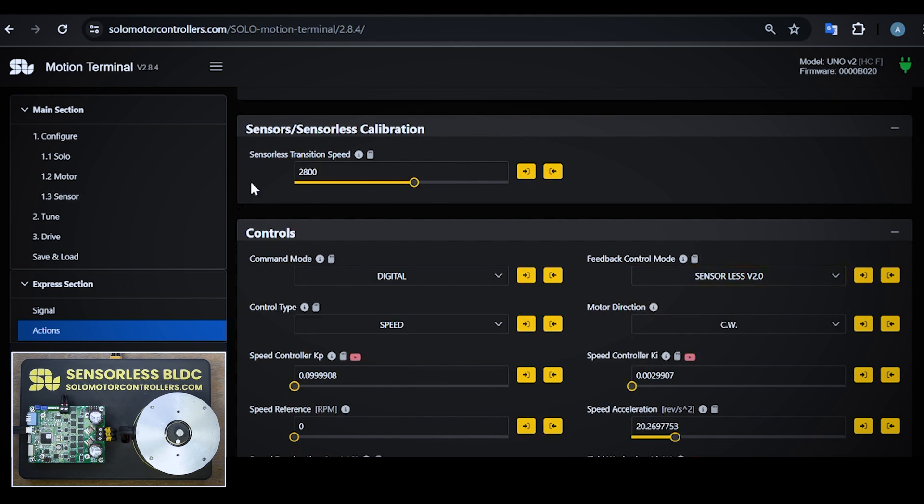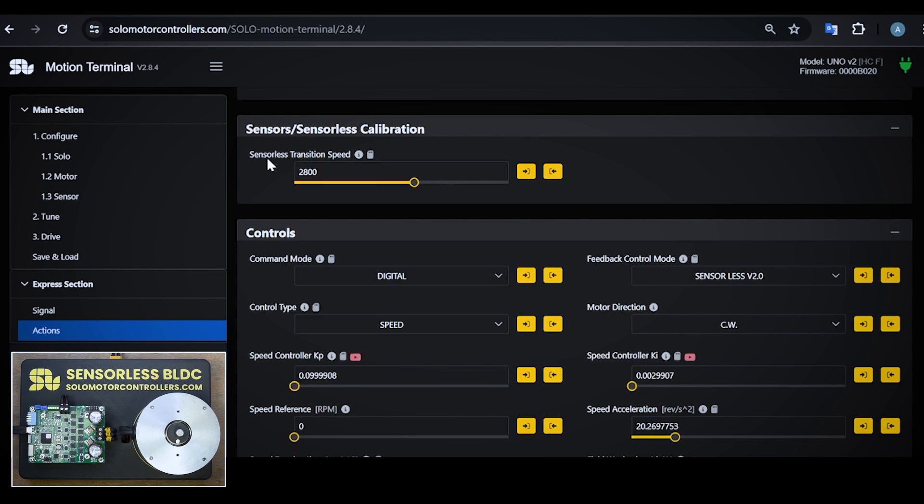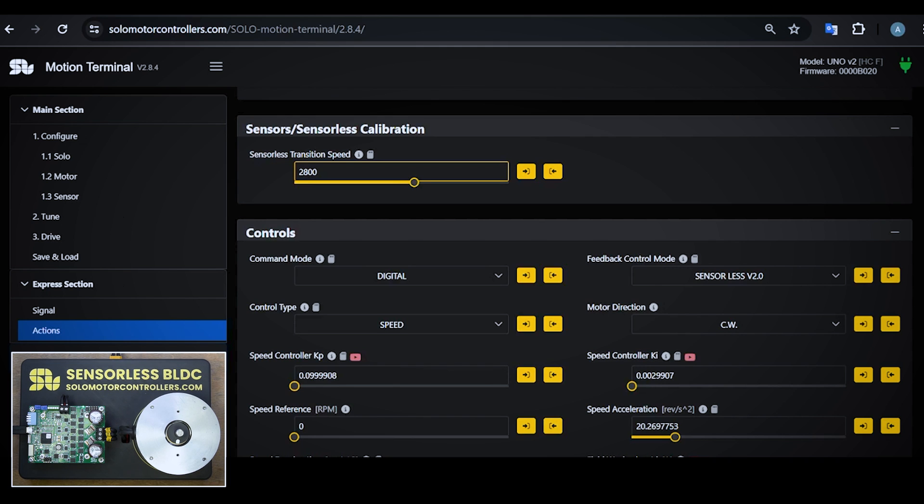After that you see a menu like this where in sensor and sensorless calibration panel you see a parameter which is called transition speed. This is the speed that we go from partially closed loop to full closed loop. As a rule of thumb, it's usually around 20% of the nominal speed of the motor. So this motor is 16,000 rpm - something around 2500 or 3000 rpm is enough. You can certainly go lower, you need to tweak a little bit, but usually starting with 20% is a very good start.